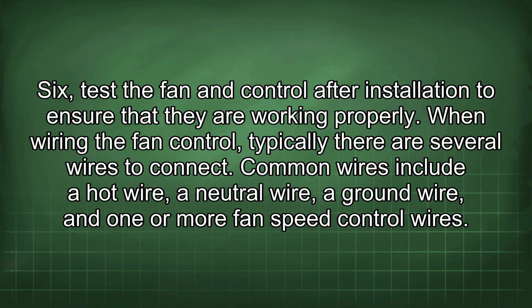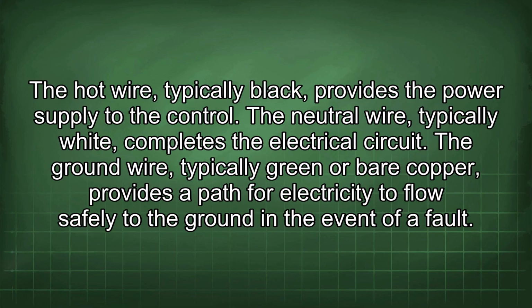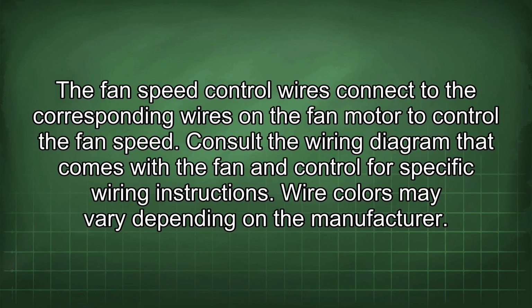When wiring the fan control, typically there are several wires to connect. Common wires include a hot wire, a neutral wire, a ground wire, and one or more fan speed control wires. The hot wire, typically black, provides the power supply to the control. The neutral wire, typically white, completes the electrical circuit. The ground wire, typically green or bare copper, provides a path for electricity to flow safely to the ground in the event of a fault. Fan speed control wires connect to the corresponding wires on the fan motor to control the fan speed.